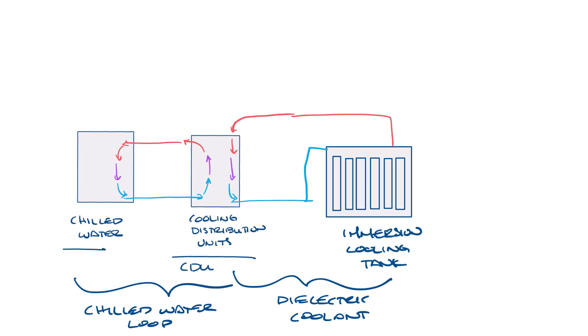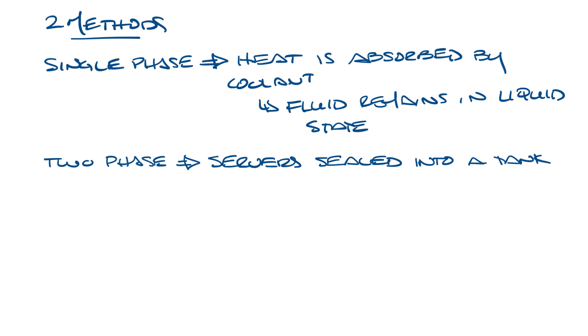Let's move this over again. So there are also two methods of heat transfer in immersion cooling, single phase and two phase. In single phase cooling, heat is absorbed by the coolant and the fluid remains in a liquid state throughout the process. In two phase cooling, the servers are sealed into a tank. The liquid has a low boiling point and the heat turns the liquid into gas, causing a phase change.